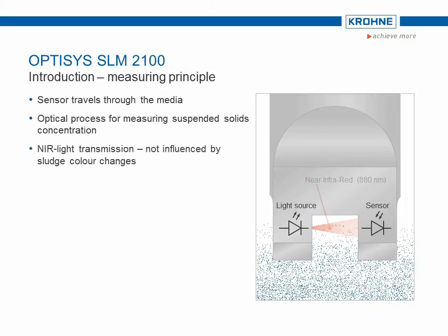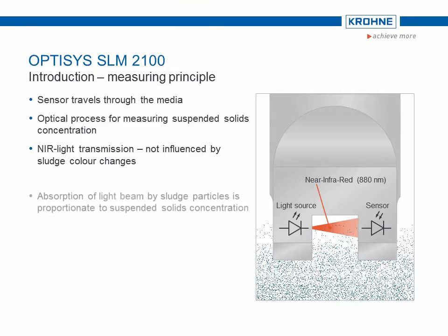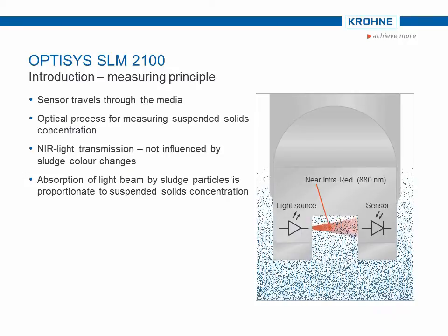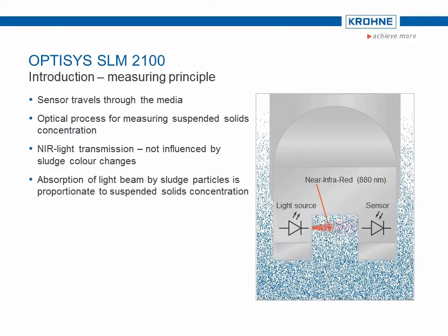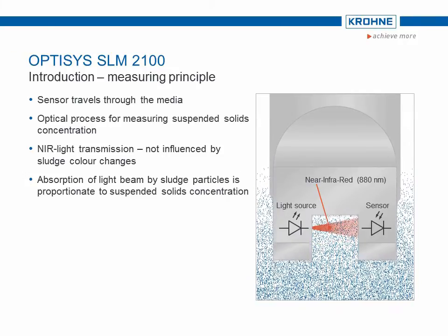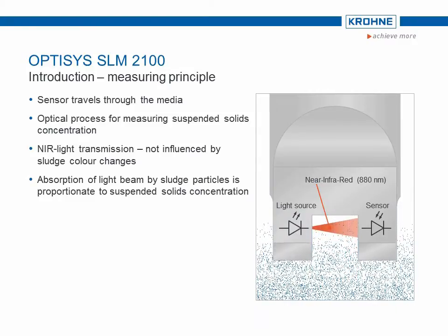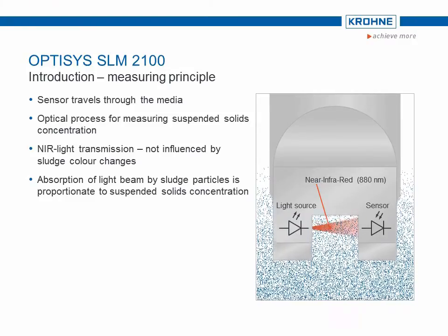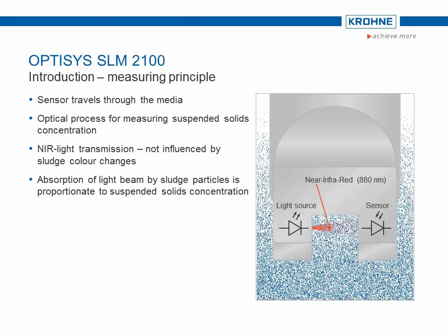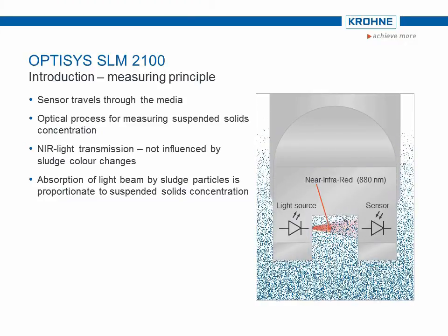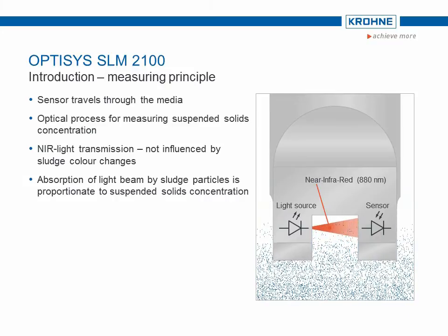The suspended solids concentration is measured using transmitted infrared light, which delivers precise measurements regardless of sludge colour changes. The medium to be measured is penetrated by a beam of light in the measuring gap of the sensor. The suspended solids and sludge particles absorb or reflect the light and thus weaken the intensity of the beam. The attenuation of energy between the light source side and the receiver side of the measuring gap correlates directly to the level of concentration of particles, which can then be easily calculated.